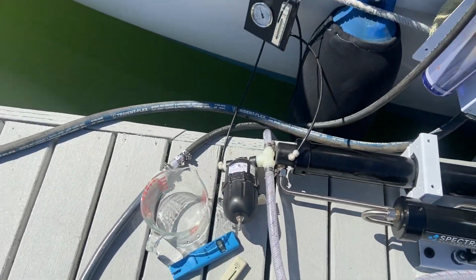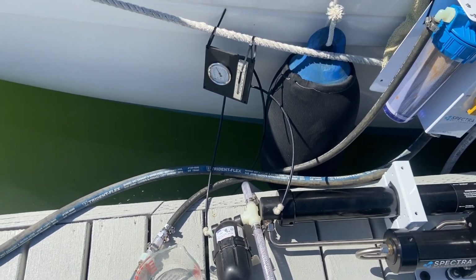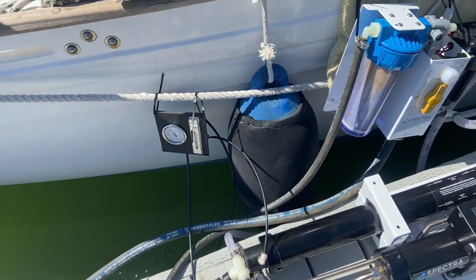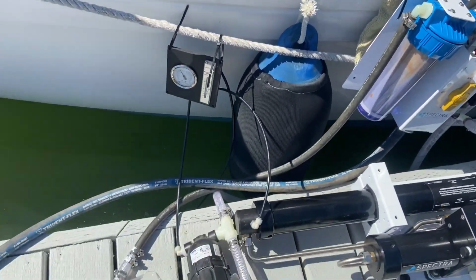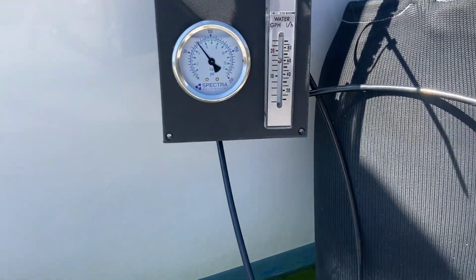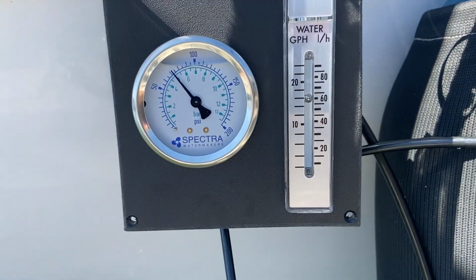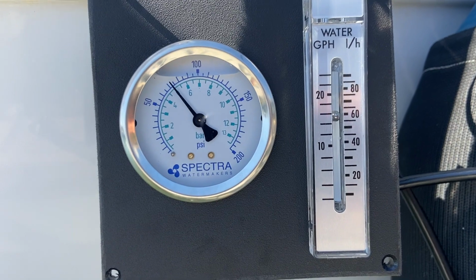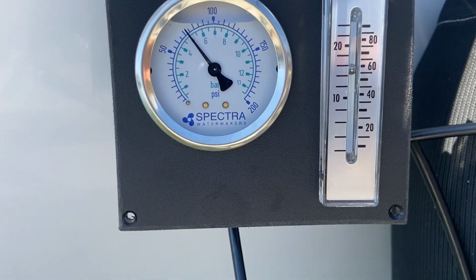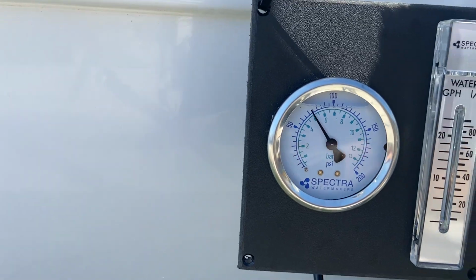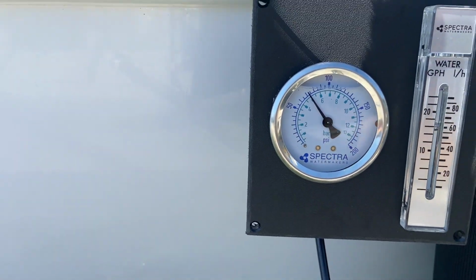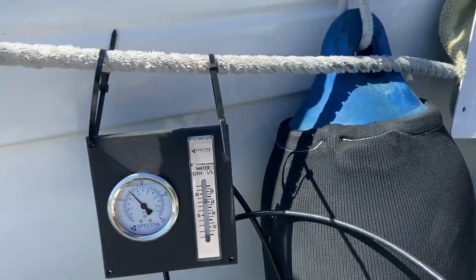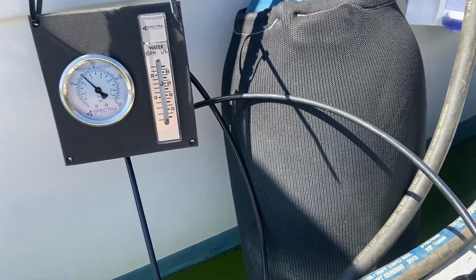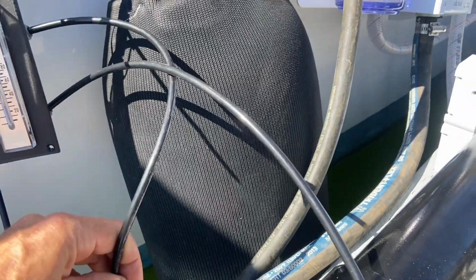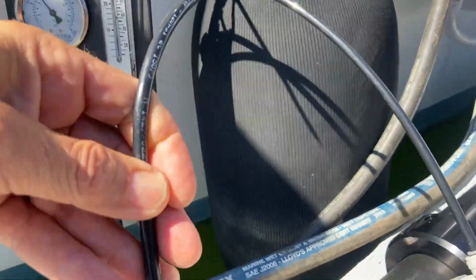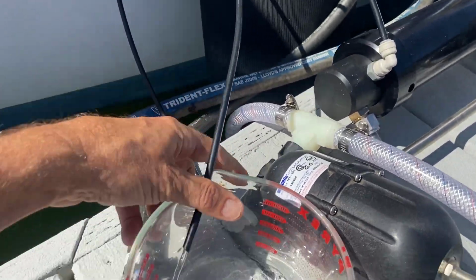So let's do a water sample and look at the gauges. Strangely, we're performing a bit above spec. It's putting out about 16 gallons an hour. It's only supposed to put out 15. And our pressure is just over 75, and it's supposed to be 90. So I can only assume that the water here in San Francisco Bay isn't quite as saline as the open ocean. We do have two big rivers that come in. So let's take a water sample here.